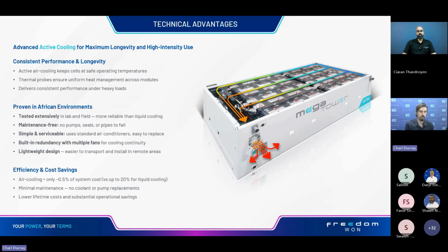On the cost side, the air cooling system we use on the megaTower only accounts for 0.5% of the system's overall cost, versus if we went the liquid cooling route, it would probably be about 20% higher in terms of the overall cost of the megaTower. I've seen liquid cooling fail on batteries previously, and when it does fail, it fails catastrophically. So we've eliminated that risk of liquid cooling failures and shorting of the system by going the route of fan cooling, which works very well.